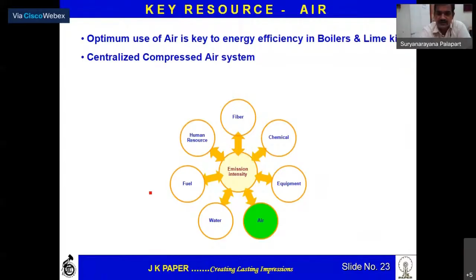Next precious resource is air. The case study I'm presenting is the centralized compressed air system. After expansion, we had one compressor house for the new plant and one for the old plant. We took one of the two rotary compressors running in the old plant and brought it to the new plant, then stopped the entire old plant compressor house, saving around 24% of our compressed air power.